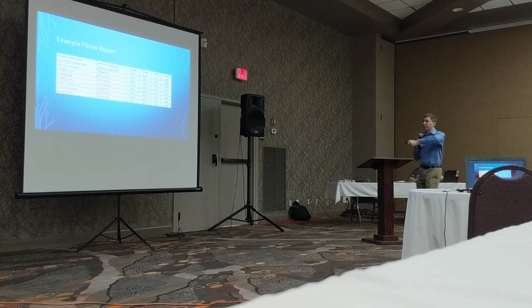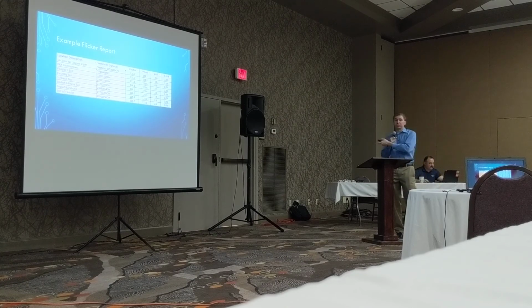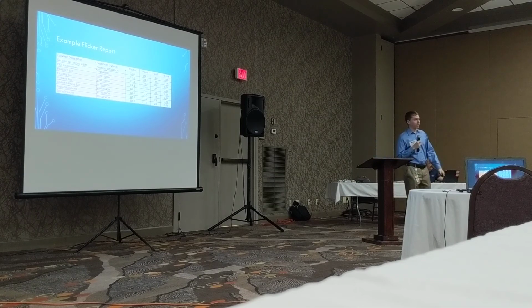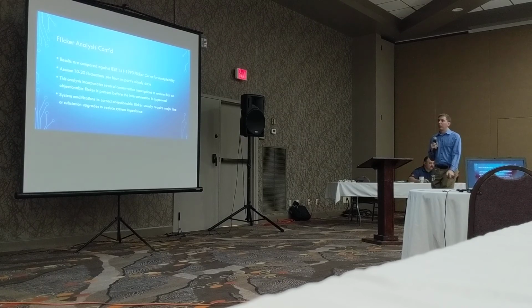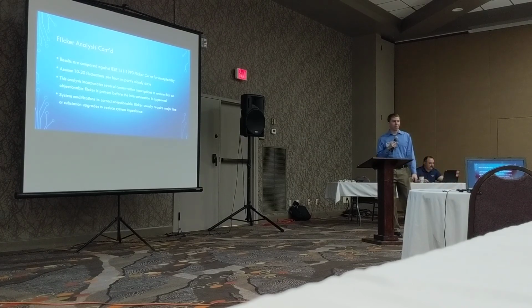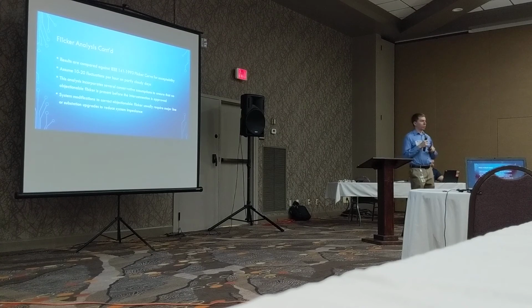So here's an example that I calculated for one of ours where it shows we've got our different types of locations on the left side, final and initial voltage difference, and then our percent difference. And then that percent difference is evaluated against the IEEE flicker curve for acceptability. We assume 10 to 20 fluctuations per hour on a cloudy day. That's, again, a little bit conservative. For a partly cloudy day, you're not always going to see 20 dips per hour. You're not going to see 10.